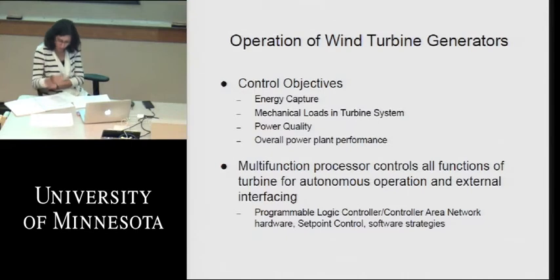where they'll feed into the central top controller as such. We want to perform a certain amount of set point control for different types of processes within the wind turbine. And again, programmable logic control is very agreeable for set point control. And we've got some other software strategies that we try to maintain. And a couple of those are the power performance curve of the wind turbine. You've got to know at any given wind what is the output in megawatts of the wind turbine. It's because this guarantees what the kind of revenue that can be calculated from that wind turbine operating in that kind of wind is going to be in that particular area.